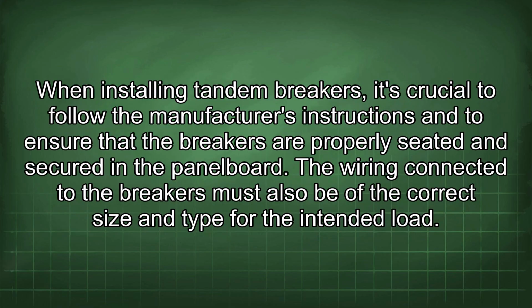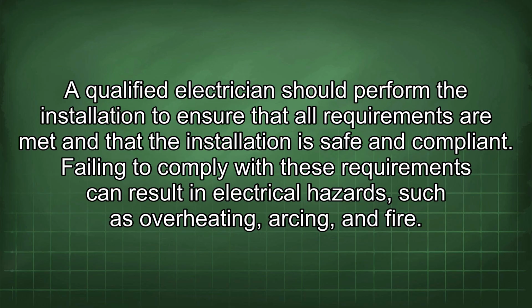When installing tandem breakers, it's crucial to follow the manufacturer's instructions and to ensure that the breakers are properly seated and secured in the panel board. The wiring connected to the breakers must also be of the correct size and type for the intended load. A qualified electrician should perform the installation to ensure that all requirements are met and that the installation is safe and compliant. Failing to comply with these requirements can result in electrical hazards such as overheating, arcing, and fire.